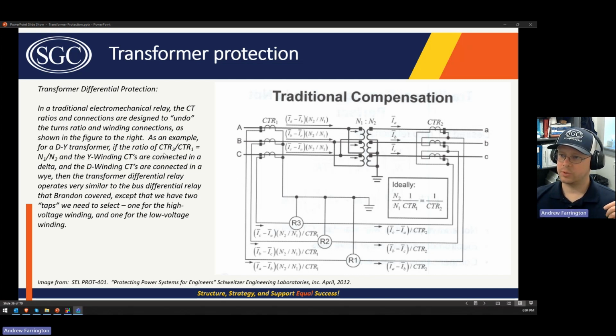So you want to size the CTs so that CTR2, which is the low side CT, divided by CTR1 is basically equal to the N1 divided by N2 ratio. Okay, and then if you connect the Y winding CTs in a delta and the delta winding CTs in a Y, you're going to undo that phase shift and you're going to account for the increased current on the Y side of the transformer.